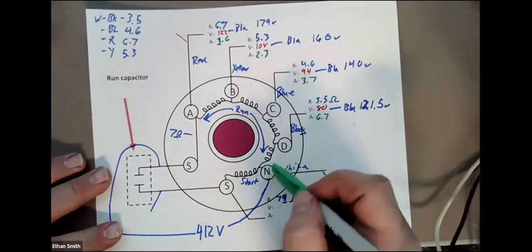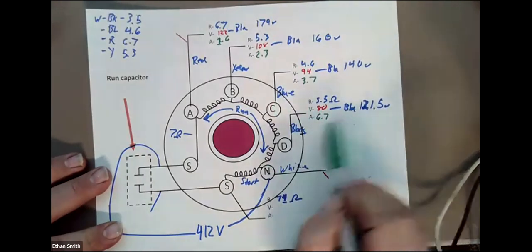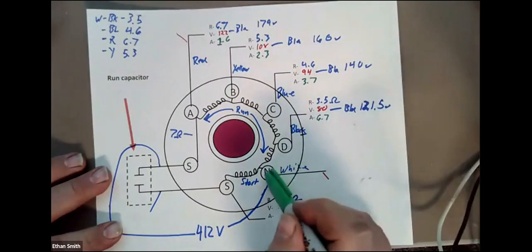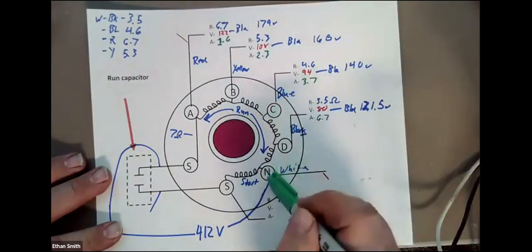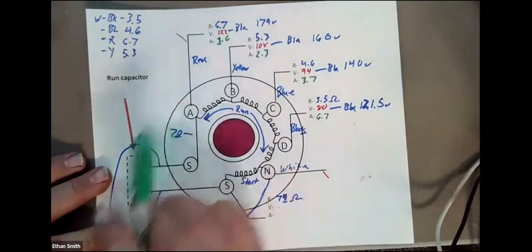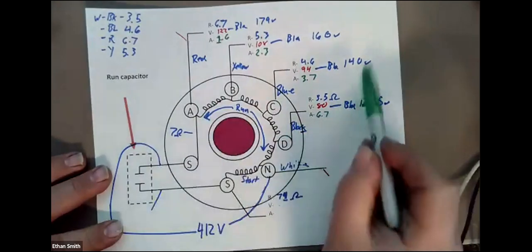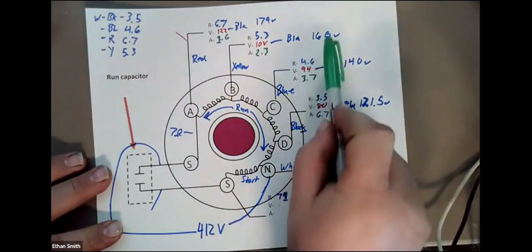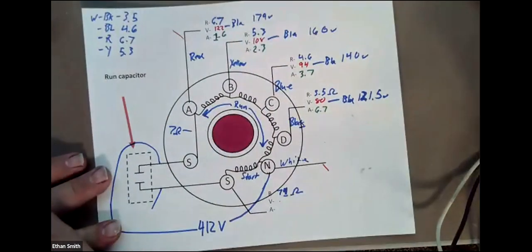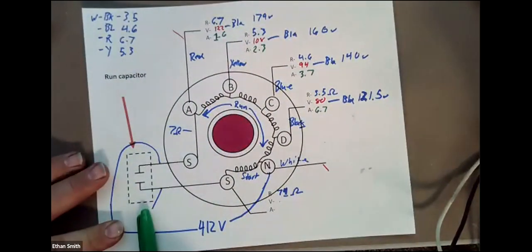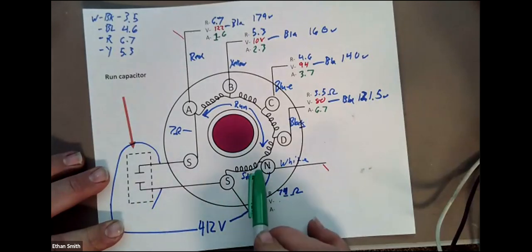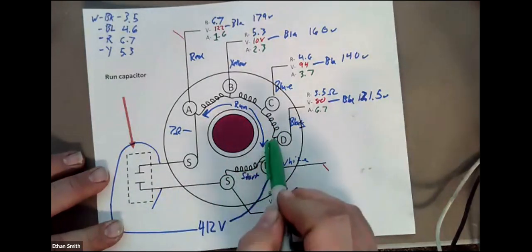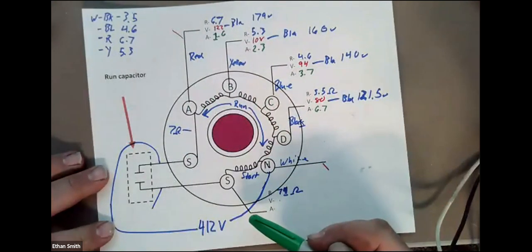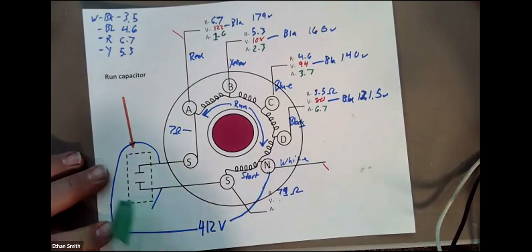When we measure voltage between neutral and black, we get our line voltage because that's where it's being utilized. But when we go between neutral and blue, or neutral and yellow, and neutral and red, we have all this extra coil generating power for us. That's why we see the voltage steadily rise: 140, 160, 179. And when we come over to our capacitor, we have that giant 79 ohm start winding plus all of this to generate power, so we get 412 volts at the terminals of that capacitor.